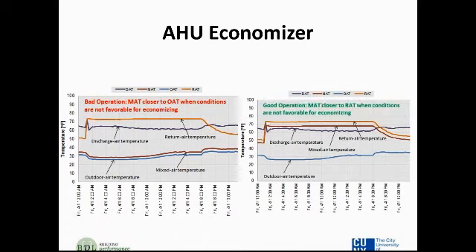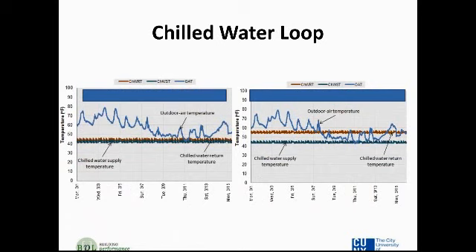So in a situation like this, if you've got a discharge air temperature that's way up in the 60s or 65 degrees, you're having to reheat that air dramatically. You would be far better off bringing in a lot more of that return air instead of the outdoor air to create your mixed air, so you don't have to heat it as much. Once again, opportunity for energy savings because we're having to heat that air quite a bit.